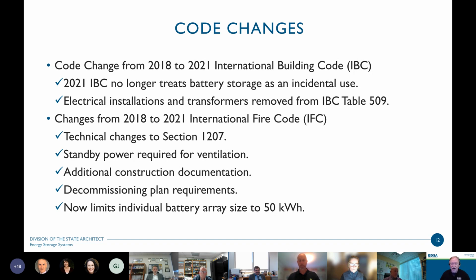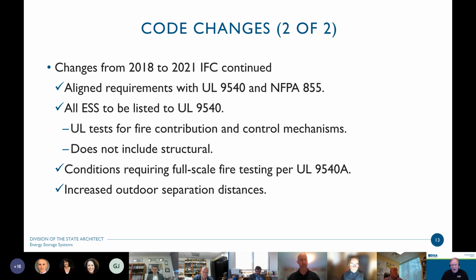And as far as the International Fire Code, again, there were some technical changes to Section 1207. A lot of that was done in coordination, again, as I said, with UL 9540 and 855. Added some standby power requirements for ventilation, additional construction documentation, some decommissioning plan requirements. And the big kicker is that it now limits the individual battery array size to 50 kilowatt hours. Continuing on, again, aligned the requirements in 9540 and 855, as I said.